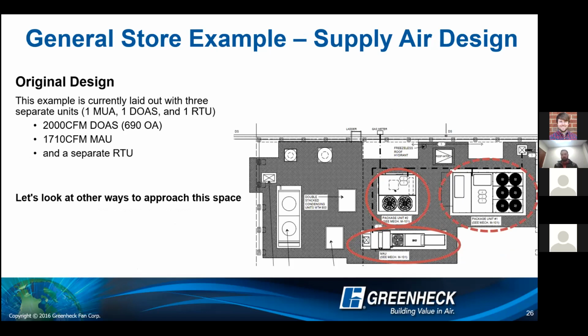So my goal is to really just show you three different ways that these are laid out. So again, a Casey's General Store. I'm not familiar with Atlanta, what your comparison would be, but these Casey's are gas stations, small footprints. So in the original design they were utilizing a direct fired makeup and cooling makeup air unit. So this was a high percentage of outside air. They were utilizing a DOAS unit, and then they were also utilizing a rooftop unit.